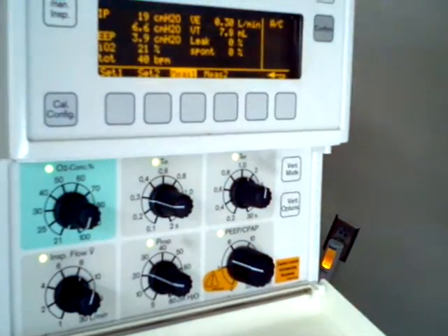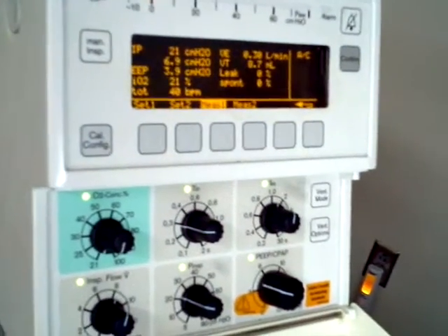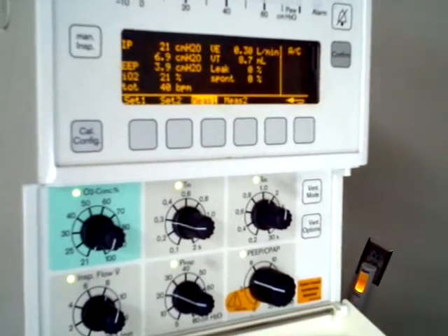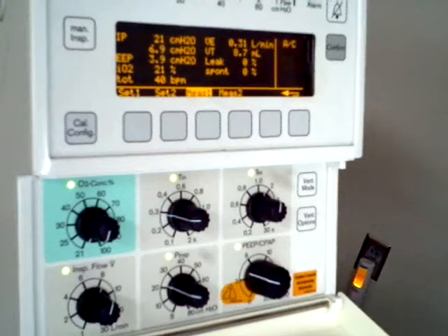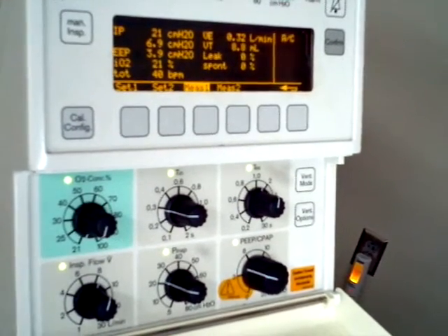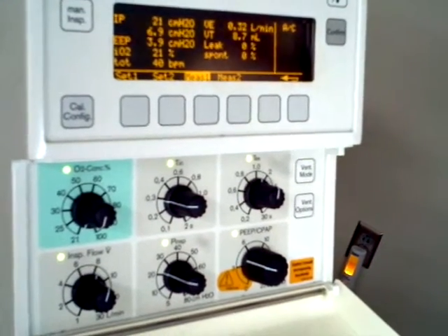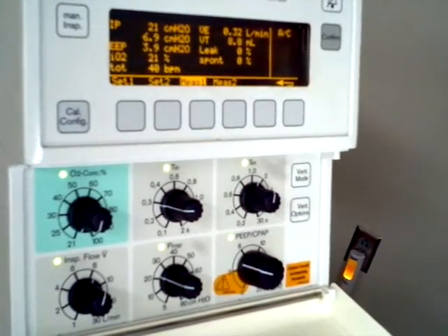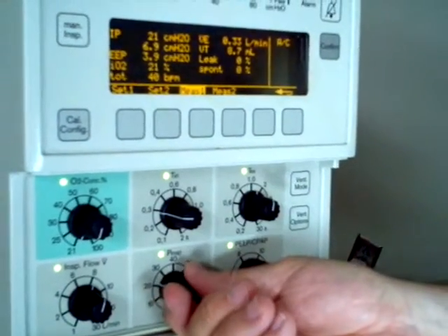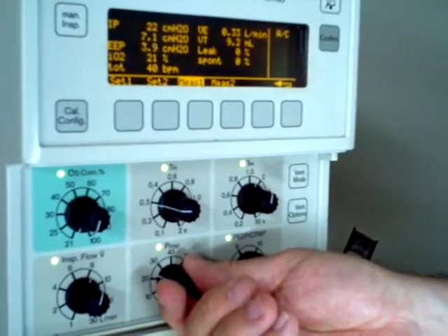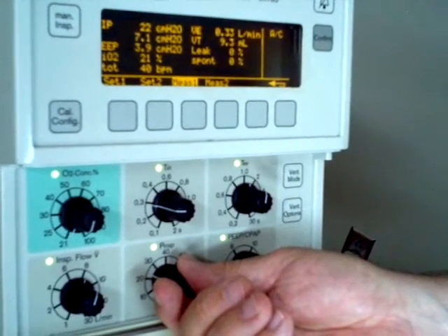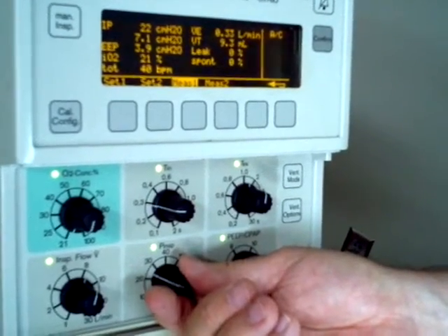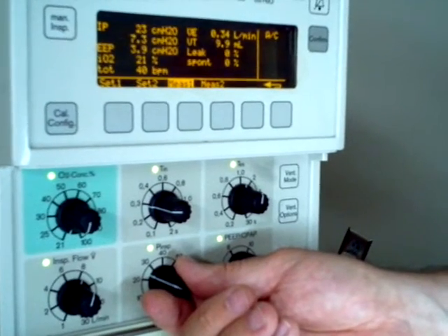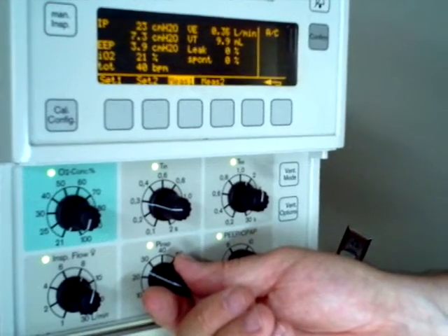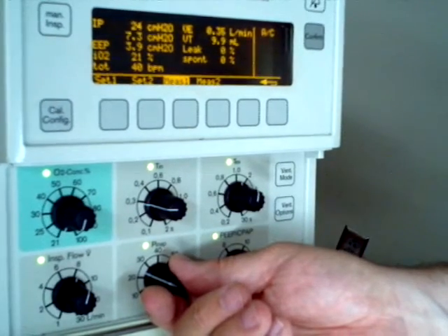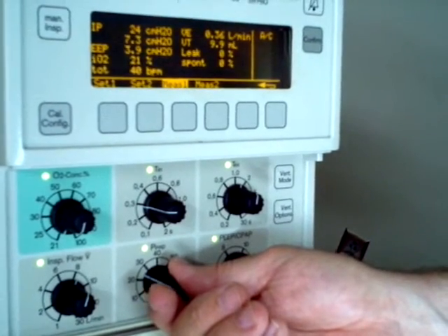Now what you need to do with this ventilator is turn it a little bit, give it a couple seconds to get up there. Don't expect to see it right away, because I'm turning a setting and it's giving me a measurement based on my setting. So it's going to take a little bit of delay. Looks like I need to go up a little bit more. And a little bit more. Now this is one where I'm not going to try to get it so that it's 10.0 on every breath. I'll be here. Well, you guys will all be gone, and I'll still be here. Let's put it that way.